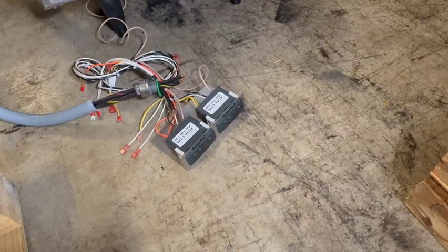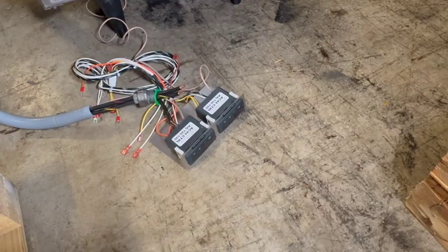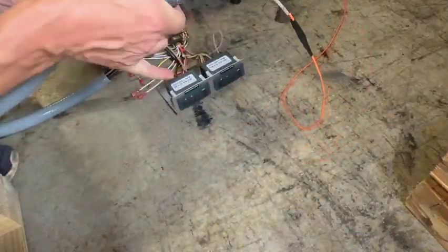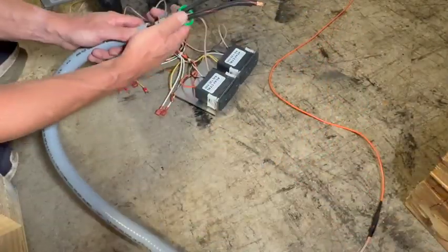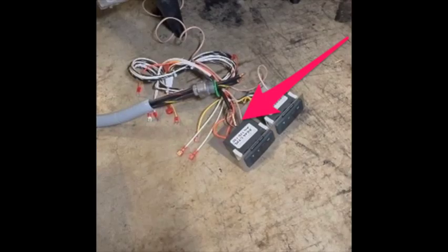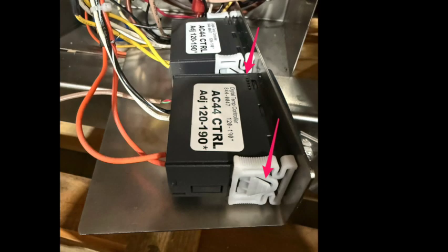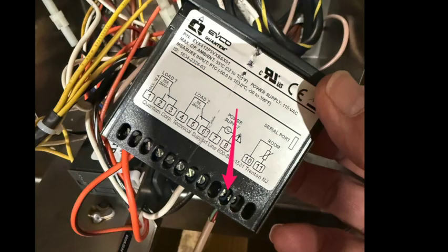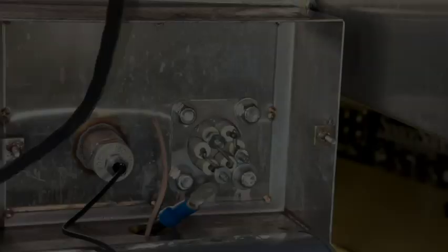So as you can see, it still took a little bit of work to get that probe wire through the conduit. Like I said, it's just really tight working conditions there. So one thing I did have to do was to take the probe wire off of the digital controller. And so here I'll show you that there's little clips on the side of the digital controller right there. If you just press those in, you'll be able to get the digital controller off the holder, and you can undo those wires.